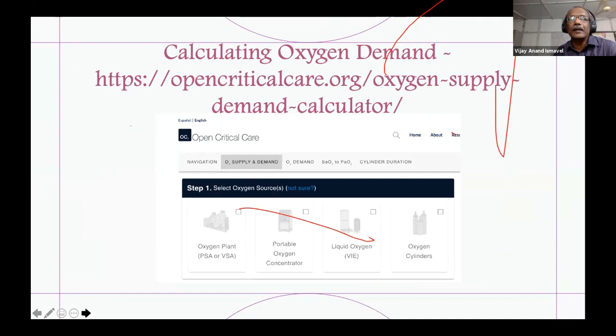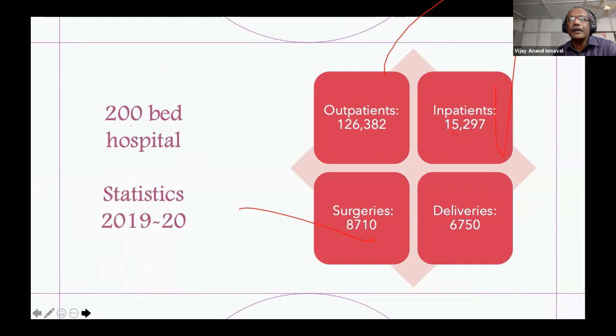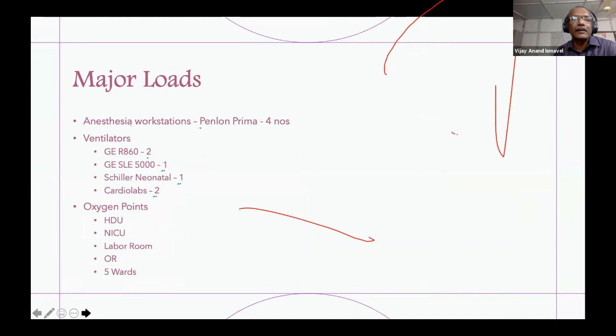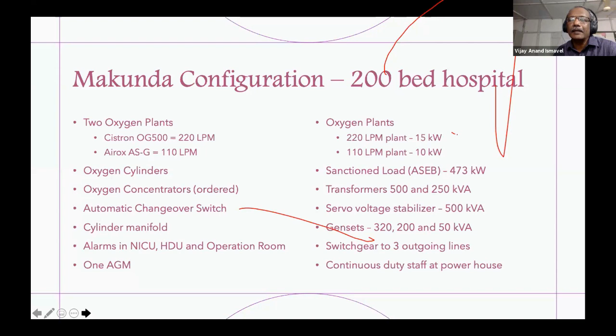Oxygen demand, I'll put up this link. So roughly how much do you need? For a hospital of our size, with these types of loads, we have all these things. We calculated and put in a 330 liter per minute oxygen plant. And on the electrical side, 473 kilowatts sanctioned load with different gensets. The correct genset should be connected, otherwise you end up wasting diesel.